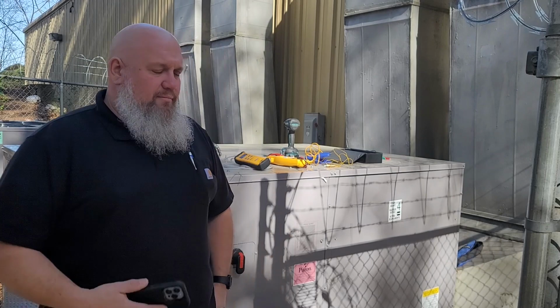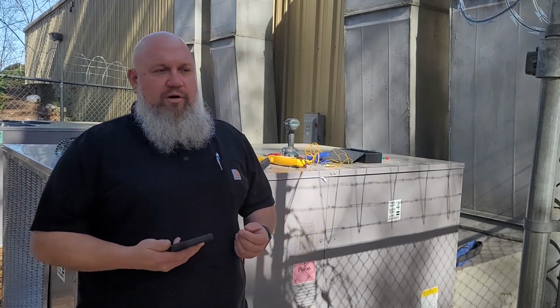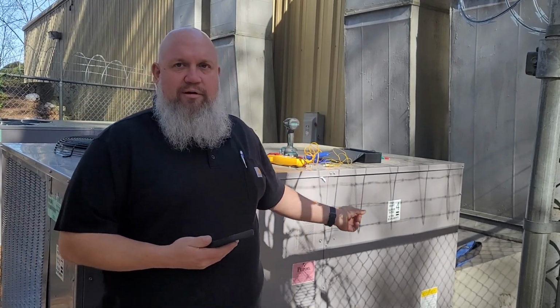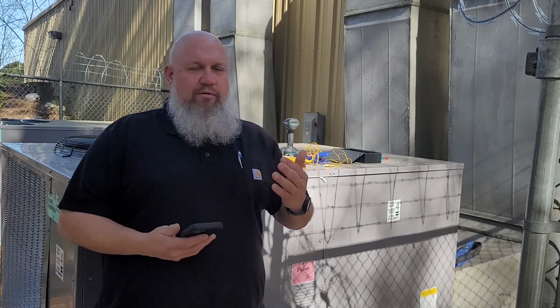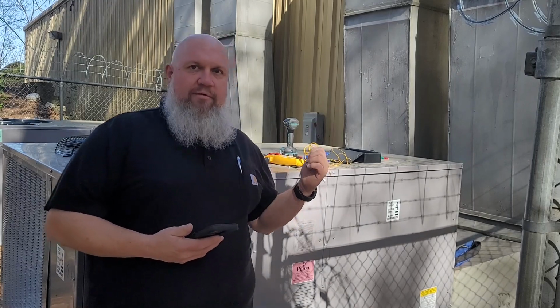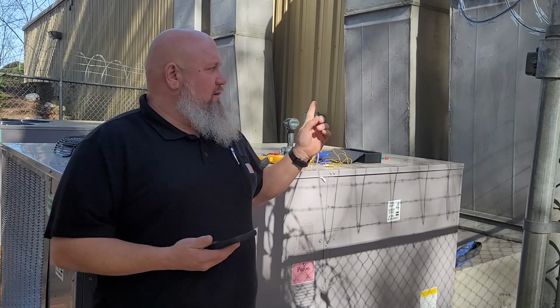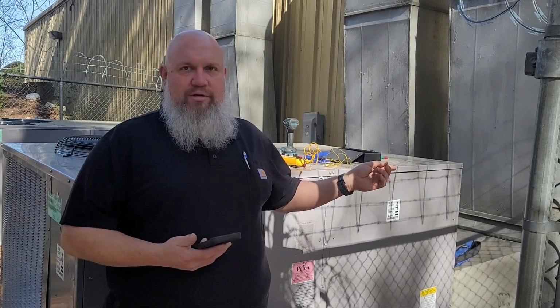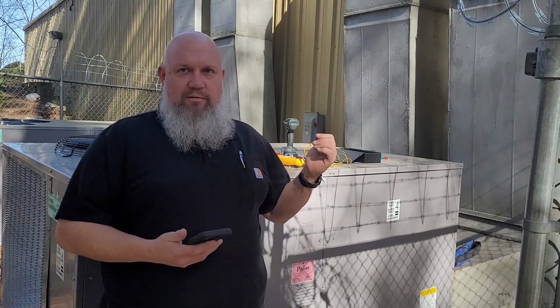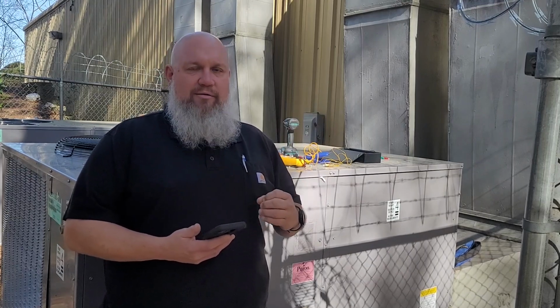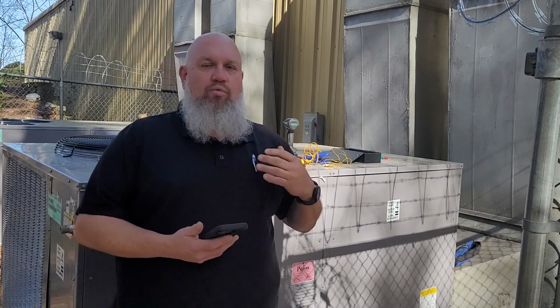What have you done so far, and how long did it take you? Initially, when you get into the form, you have to get model number, unit information, all the refrigerant statistics off of the nameplate. You got to get your disconnect information, take pictures of the unit, and just fill in all of the unit information correctly so that the system knows what you're working with before you start taking your measurements.